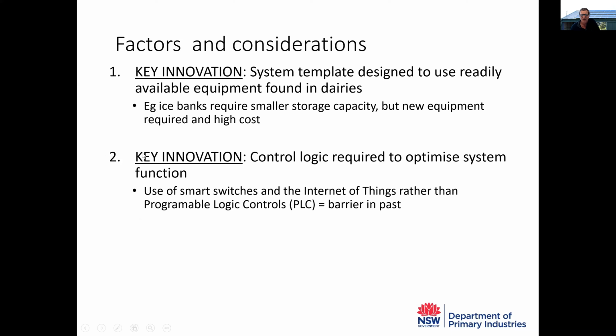The other key innovation is control logic required to optimize the system function. For example, in the morning we don't want the chiller turned on before there's sufficient solar energy generated by the PV, so there needs to be some control over that. In the past this might have been done by PLCs, programmable logic controls, but this has been a barrier because they fail and are complicated to fix. With the use of smart switches and the Internet of Things, there's potential for some of these barriers to be lifted.